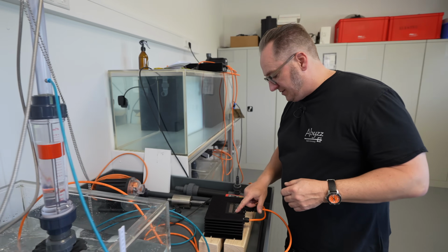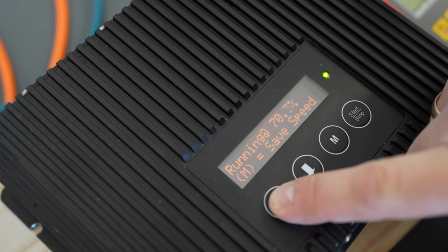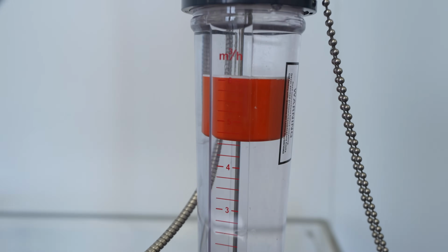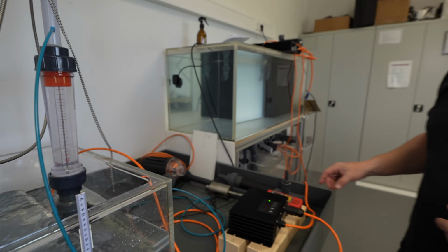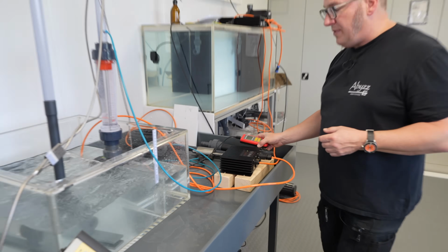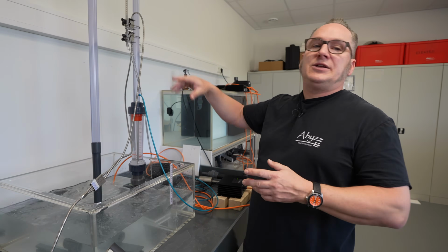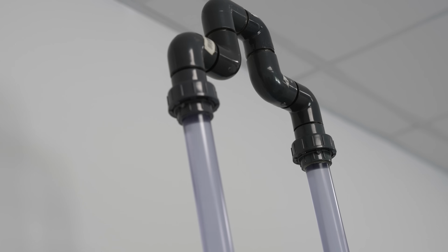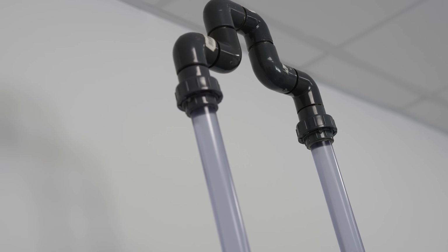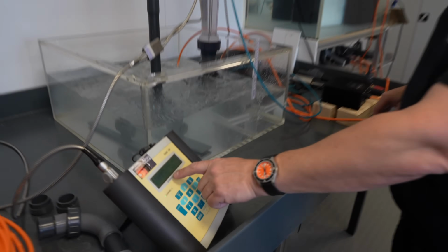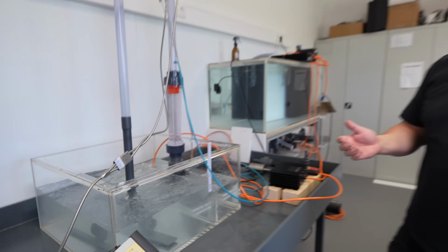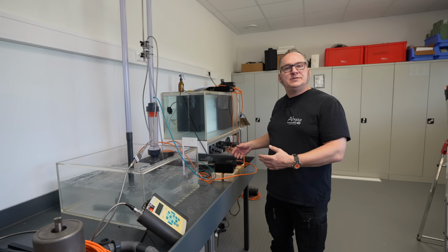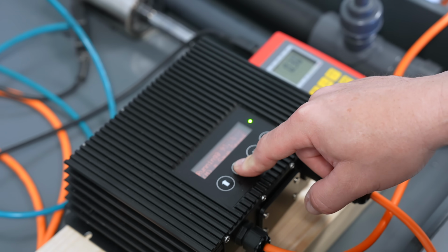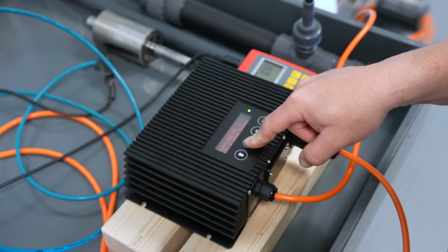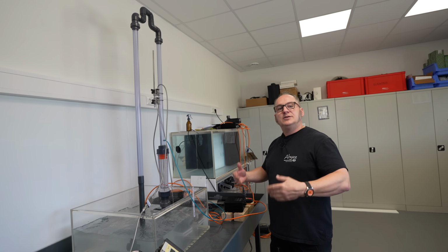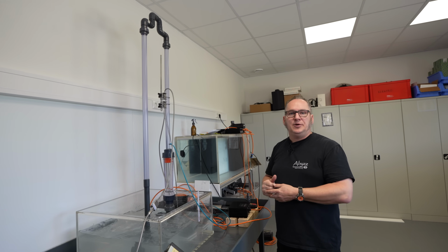Now we'll show you the biggest difference if we dial up the pump to full speed. Let's see how much the plumbing can take and how much the pressure against that is going up. We have a pressure of 0.25 bars, which is 2.5 meters, in a system that shouldn't have any head pressure. It's just friction losses right now in those PVC elbows and of course the plumbing itself. The pump is running at 100% and we are only reaching 7.3 cubic meters, whereas before it was almost 9 cubic meters. So the pump has already raised speed, so the RPMs on the pump already went up by roughly 200 RPMs due to the fact that it's not using as much energy as it should use. So then it speeds up to 100% and goes a little bit beyond. We call that an overdrive.